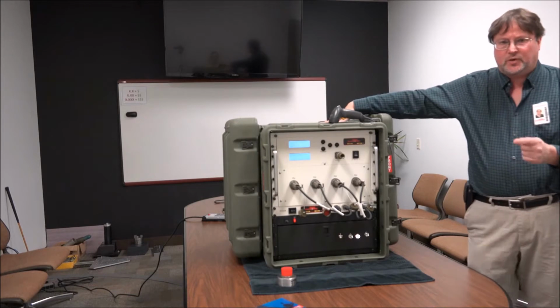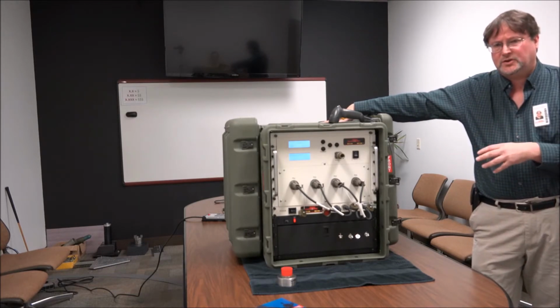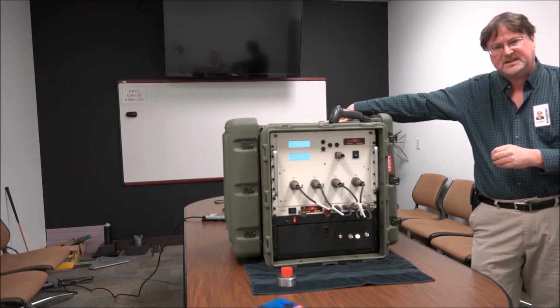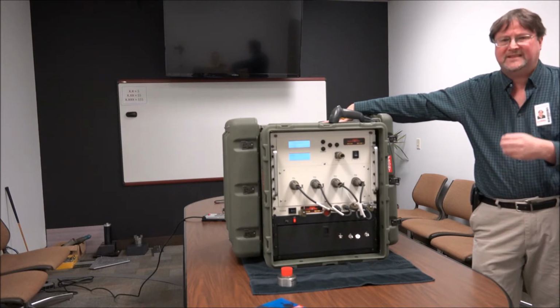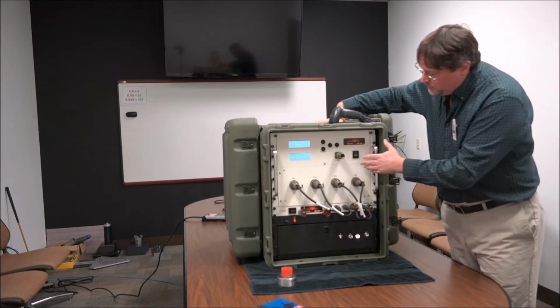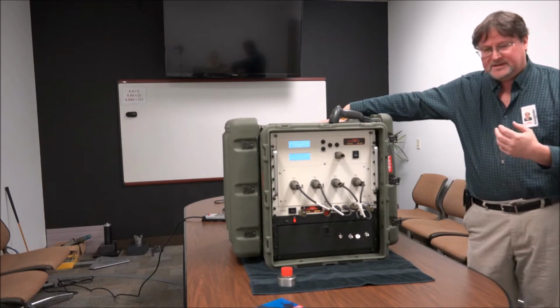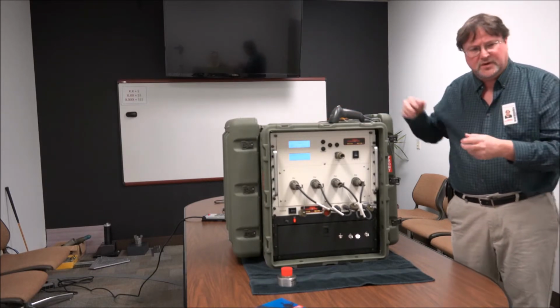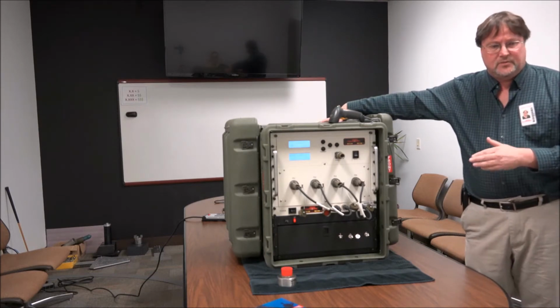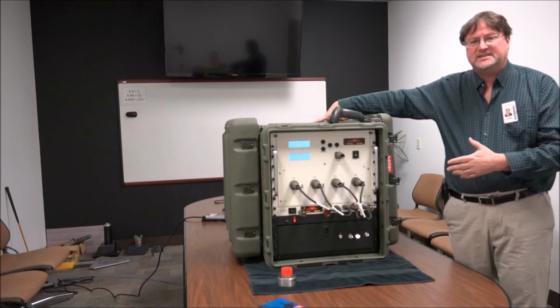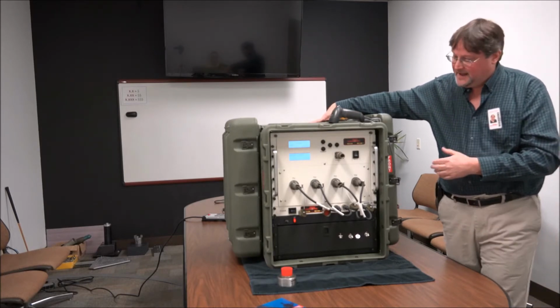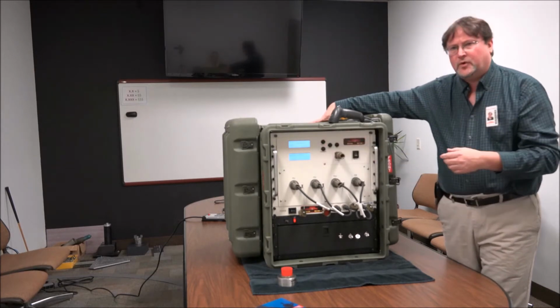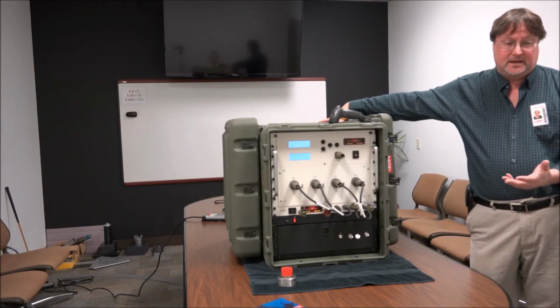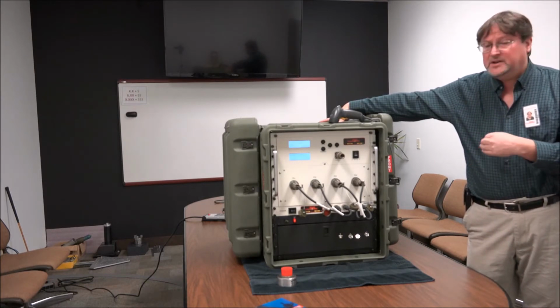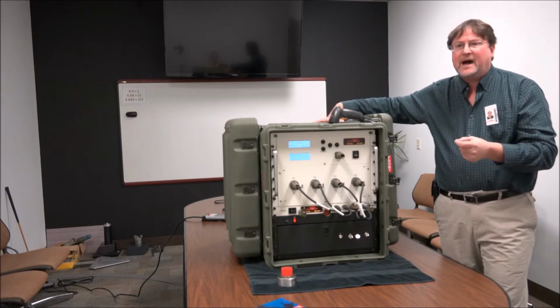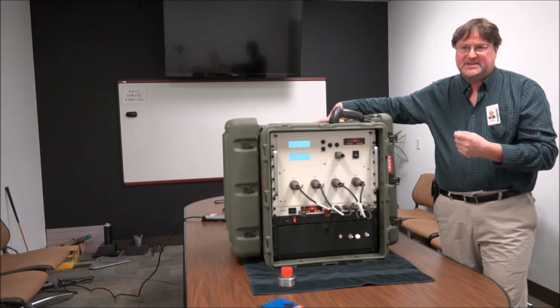These systems are all version controlled. We keep very tight control of the electrical and the mechanical designs of these so that they're consistent, and every time you purchase it, if you purchase the same model number, you get the same thing. We also control the calibration digitally. Unlike some testers where you have pots and adjustments, you have to open the unit to tweak, these aren't, they're fully digital. With a calibration kit, you can actually do calibrations in the field with this system. And since it's digital, that's one of the reasons why we also store in it, in digital form, the calibration date. So when you're interfacing this with software, we know when this unit was calibrated. So we can stop a test if the unit is out of calibration, protecting the integrity of your data.